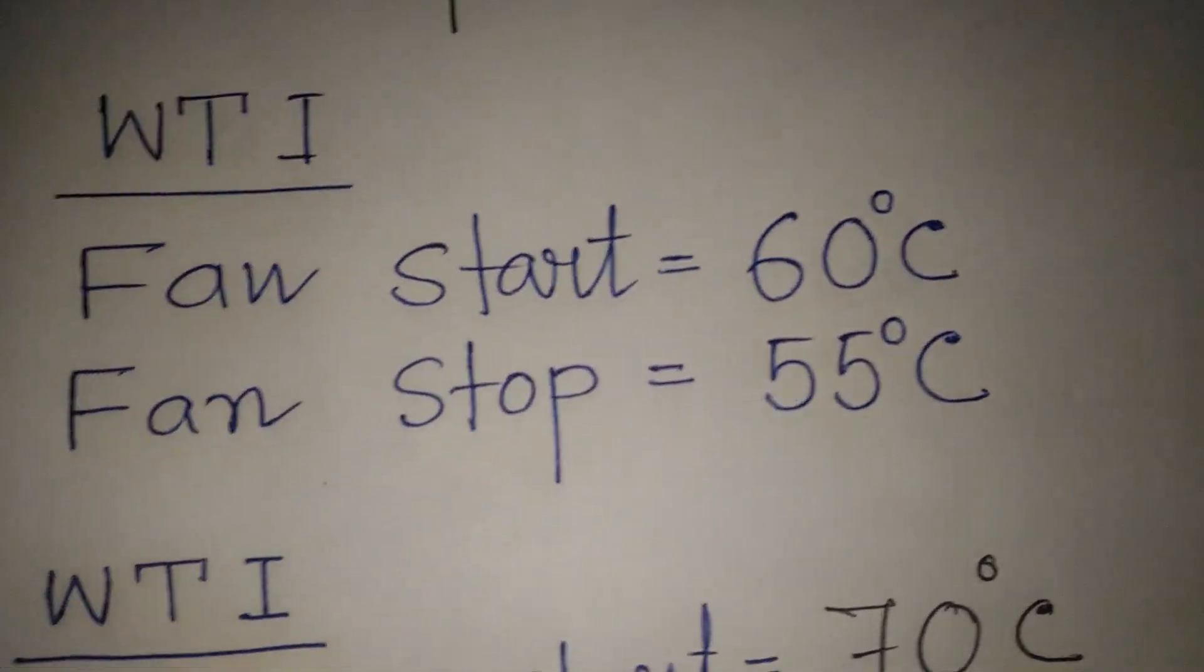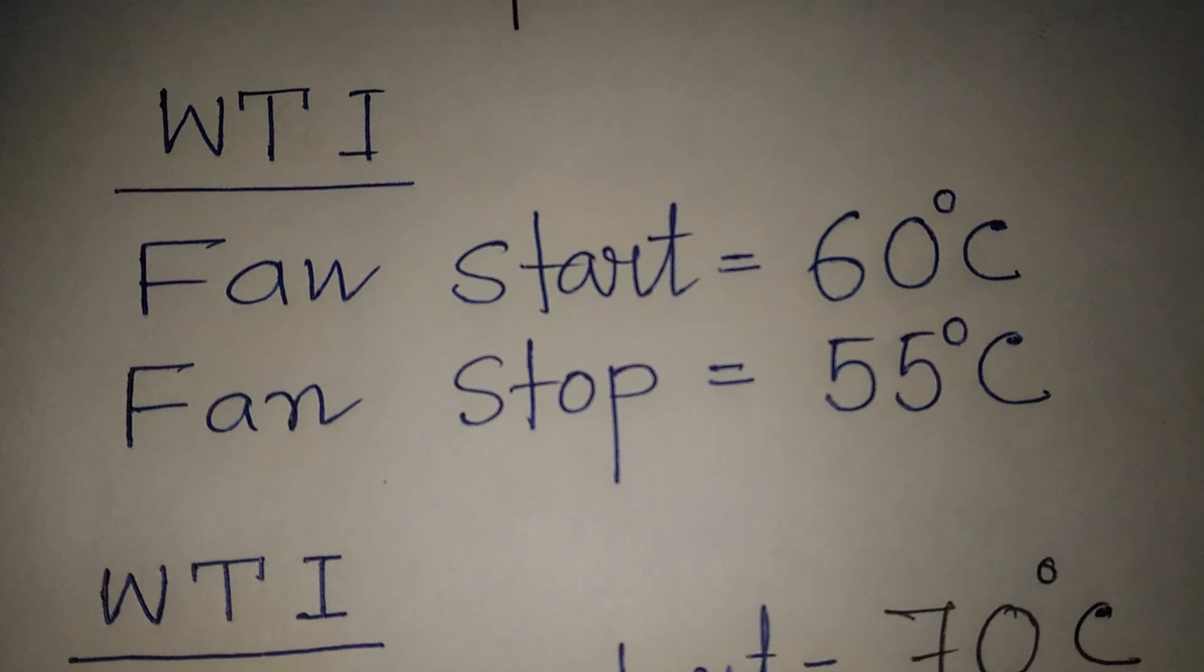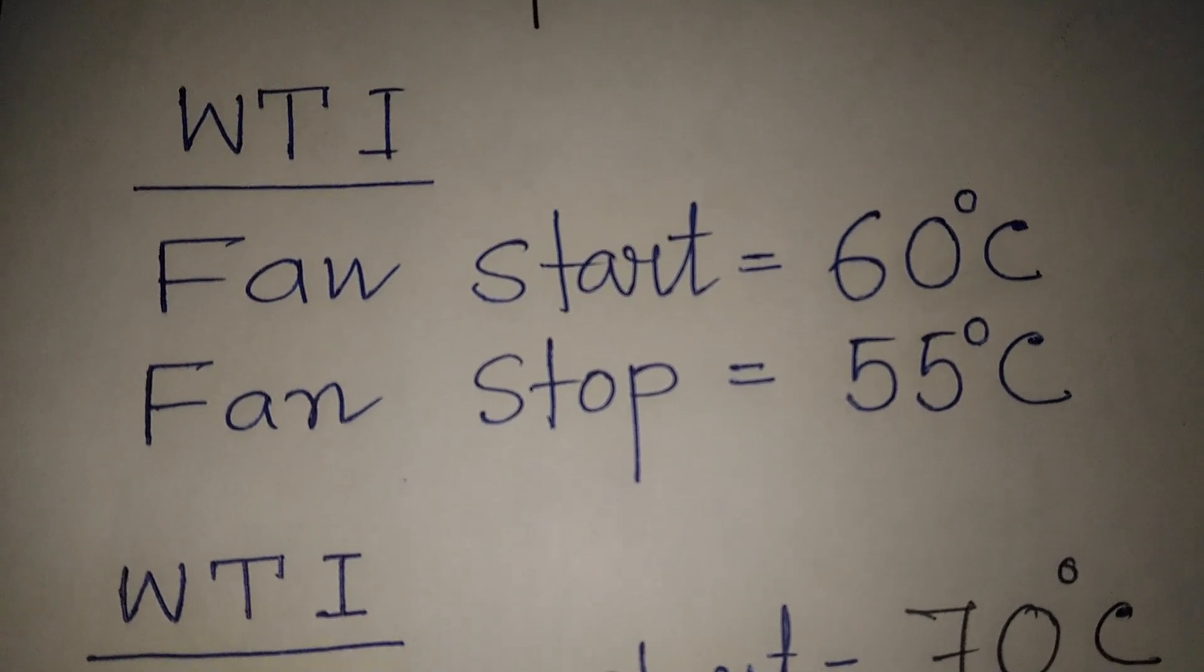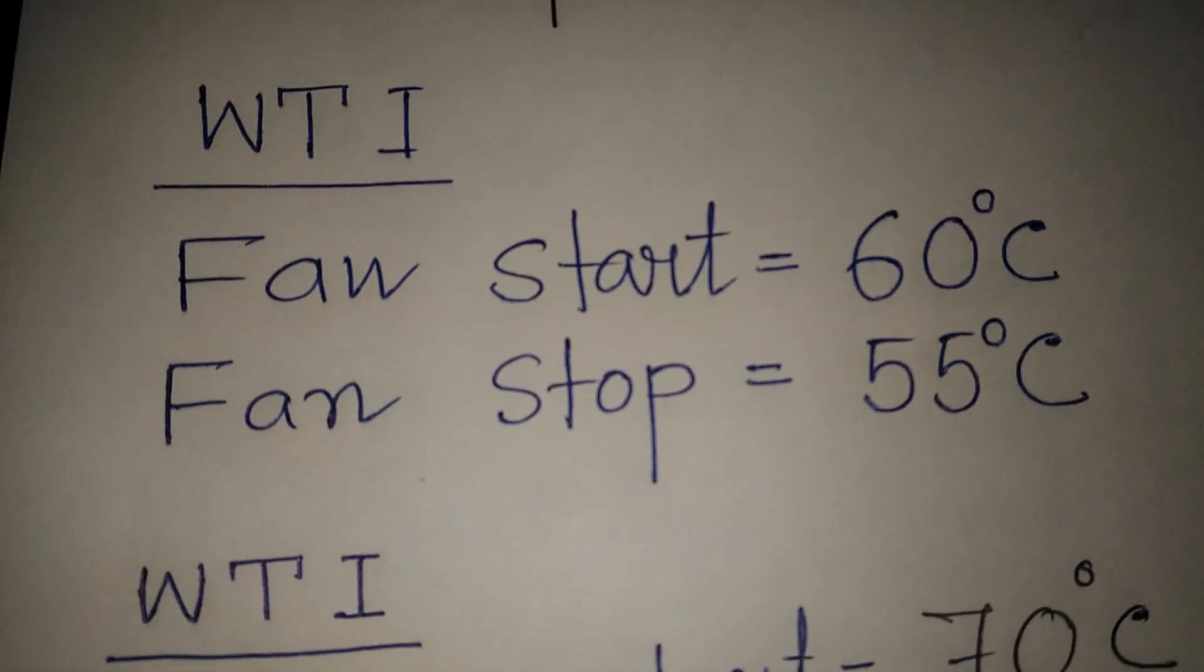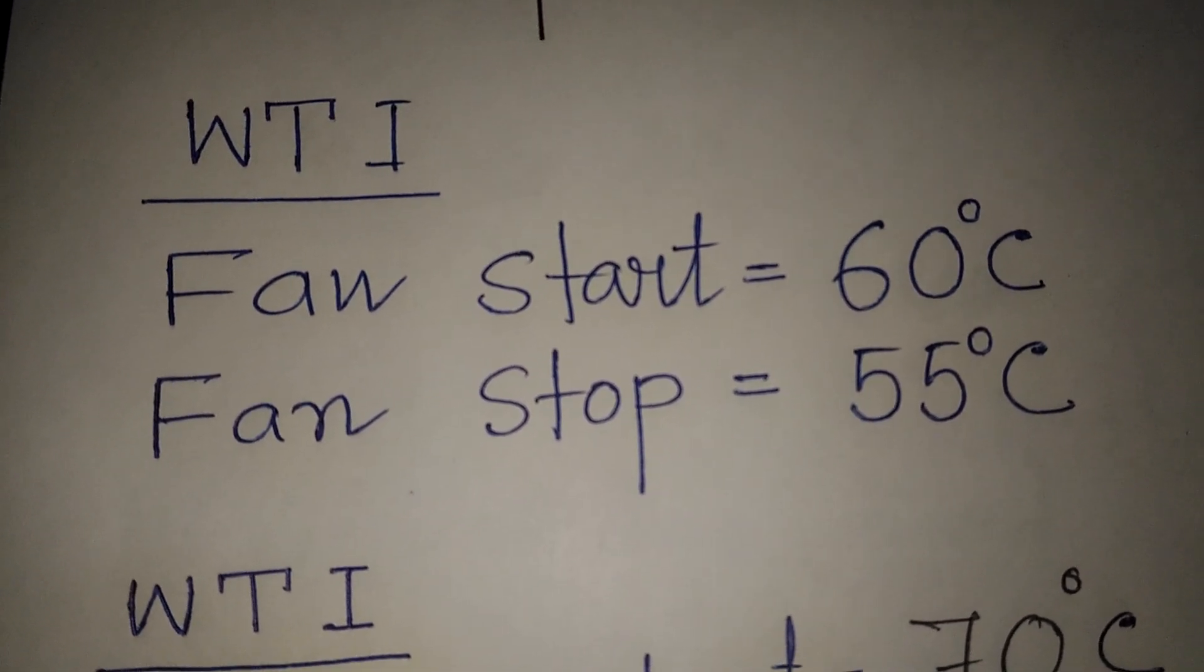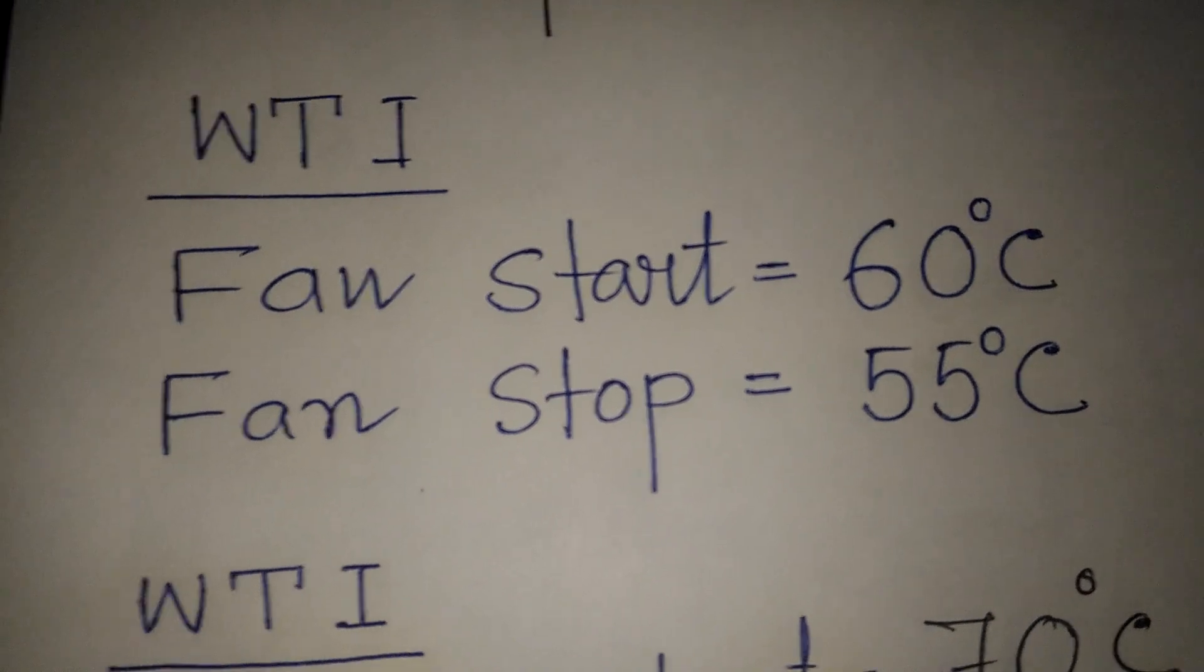WTI setting may be for the fan start is 60 degree Celsius and for the fan stop, it may be 55 degree Celsius.